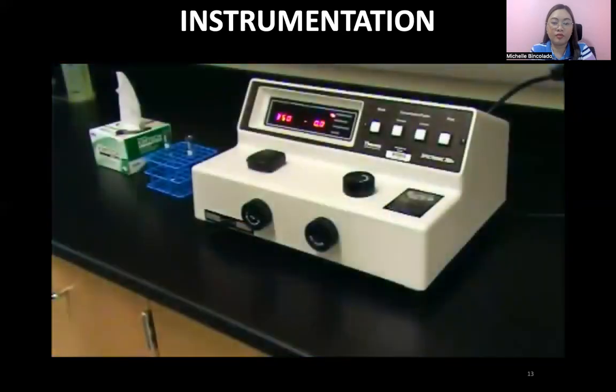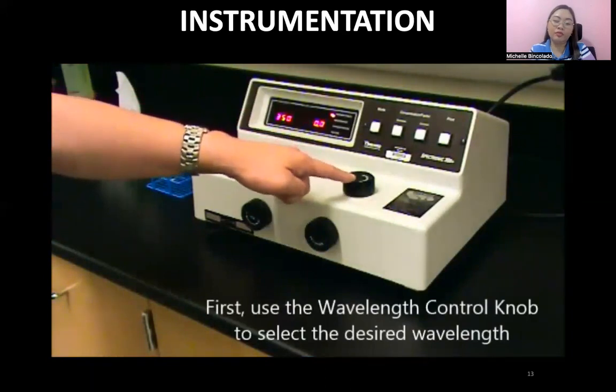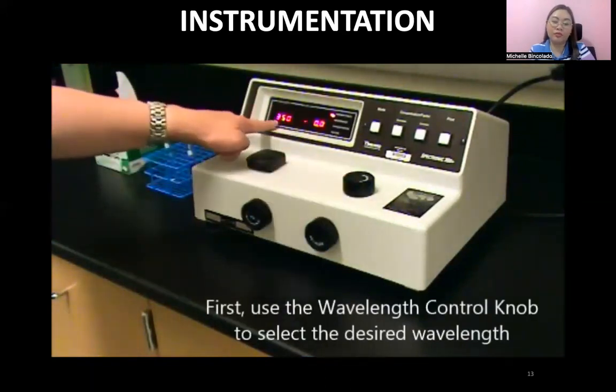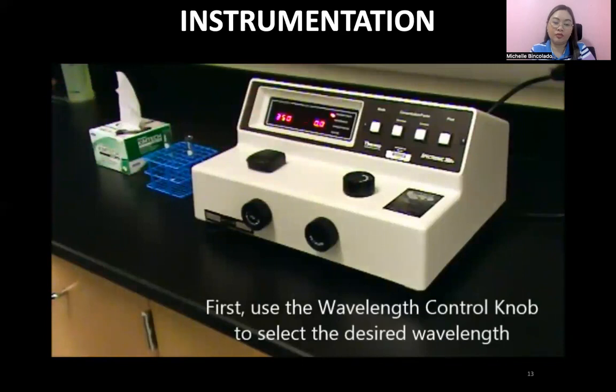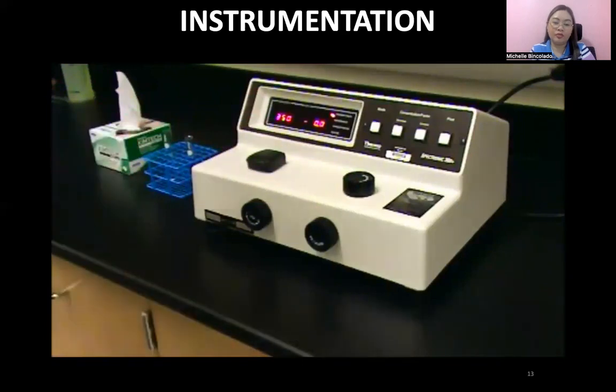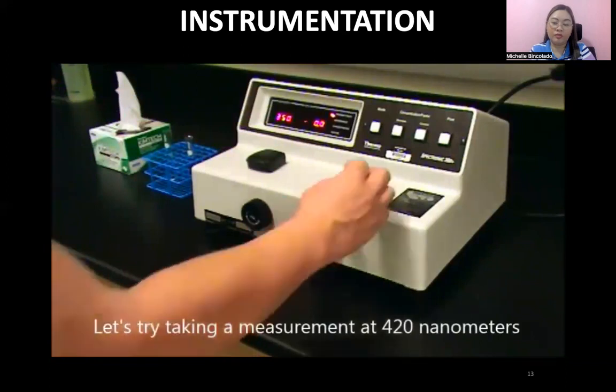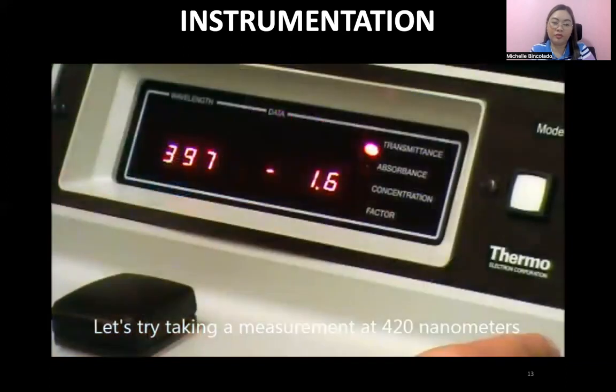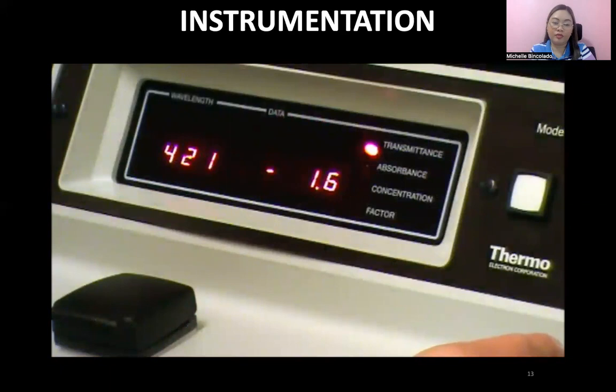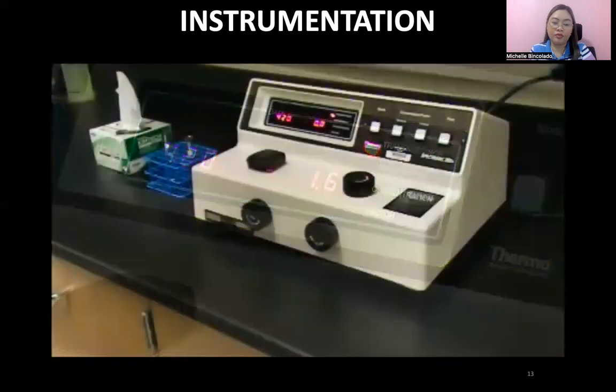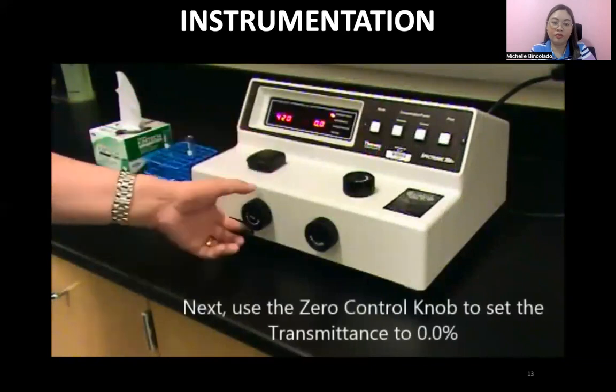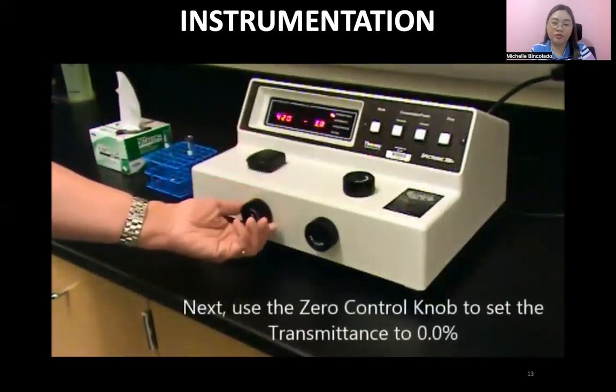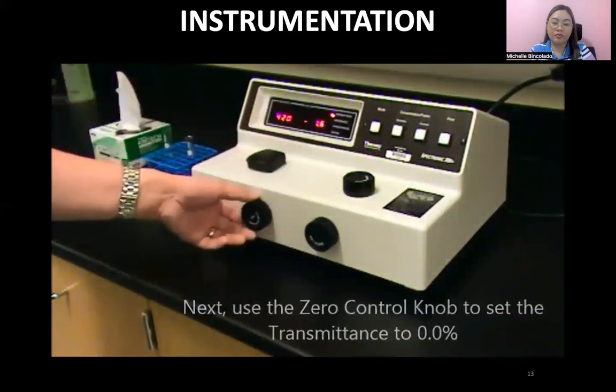In order to start taking a reading, you have to first set the machine up. So to do so, first thing you must do is use the wavelength control knob and adjust the wavelength until the wavelength that you want to measure at is reached. And let's go ahead and try taking a measurement at 420 nanometers. Next thing you need to do is, using the 0 control, turn the 0 control until you get 0.0 showing up on the display.